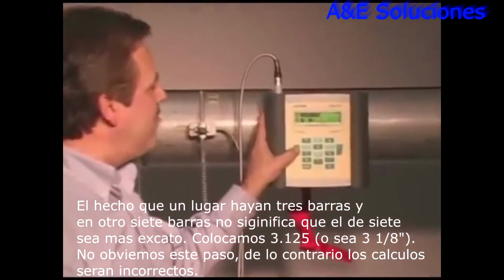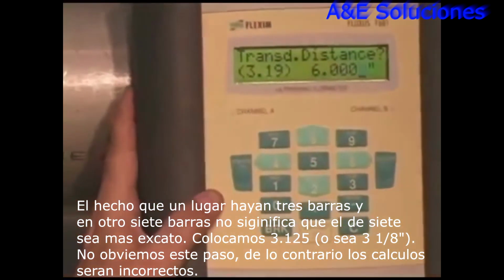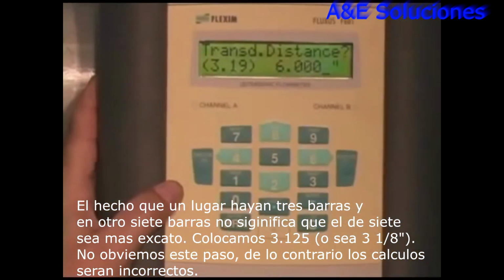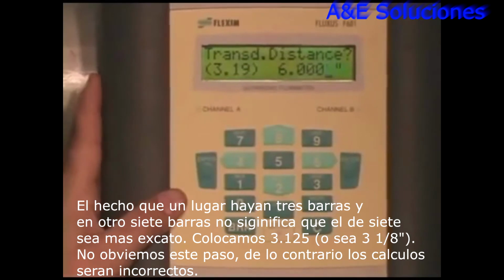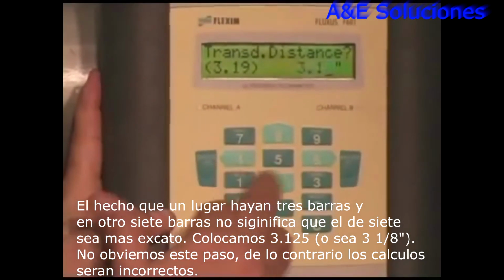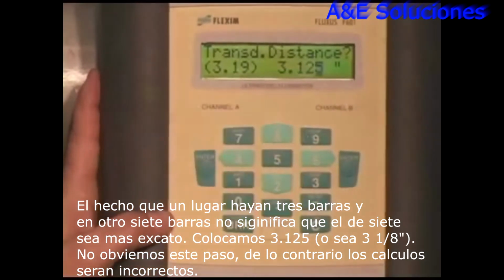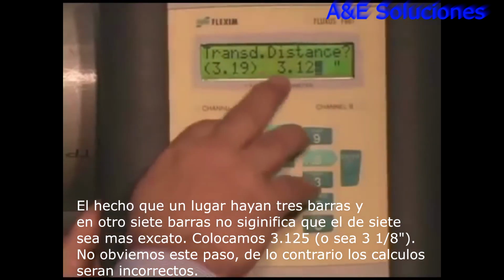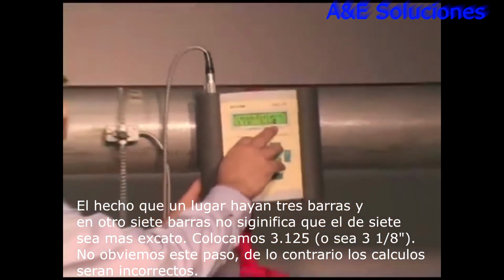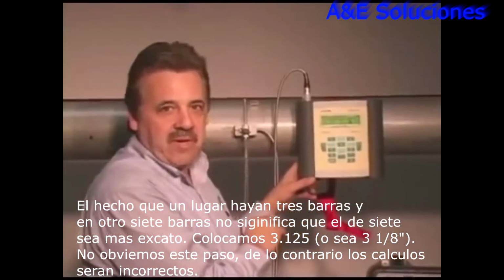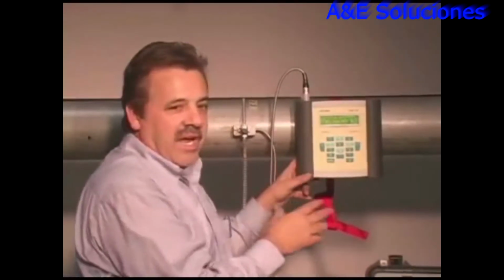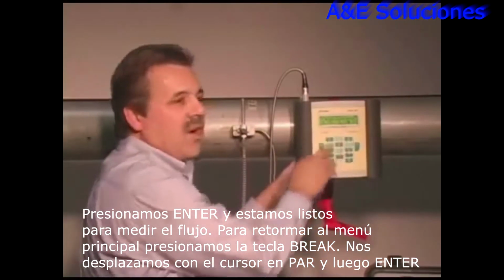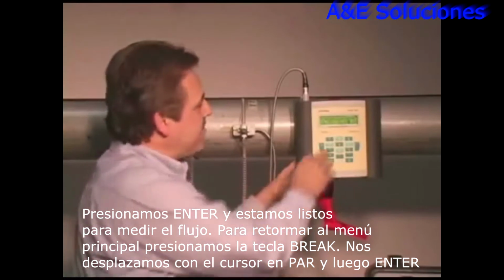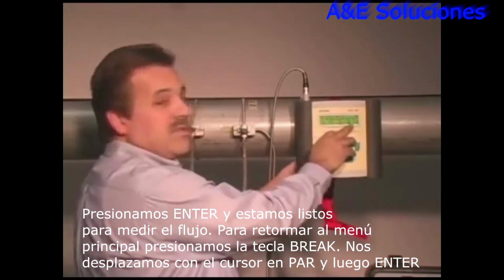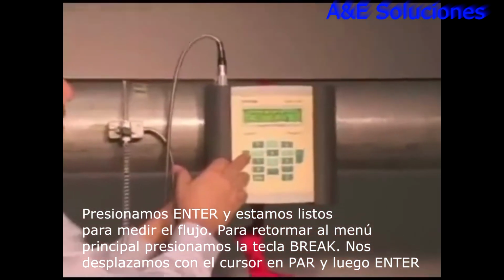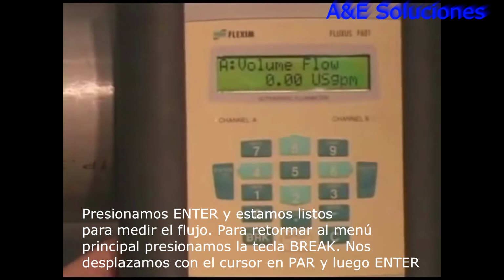I'm going to hit the enter key now, move on to the next cell. The last thing now that the meter is asking me is what distance did I space the transducers at. I put it at 3 1/8. That's 3.125. I enter in 3.125. Now don't forget to do that, because the value that was in there was the value that was there from the last time you used the meter. And if you leave that alone, it's going to do a calculation based on an incorrect distance that it thinks the transducer is at. So don't forget this step. Now you tell the meter what distance you have the transducer spaced at. You press enter, and you're ready to start measuring flow.